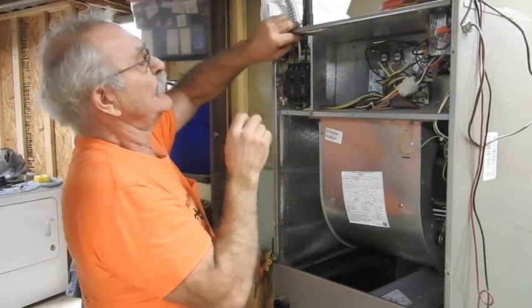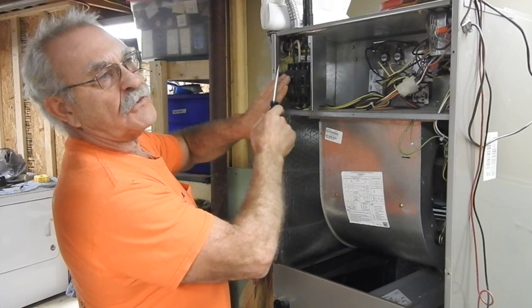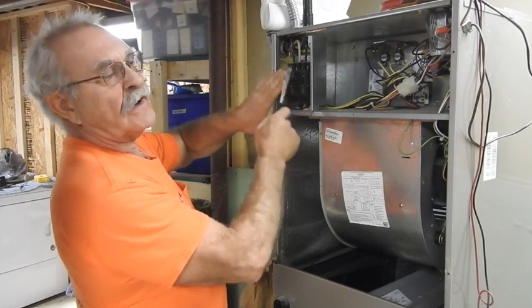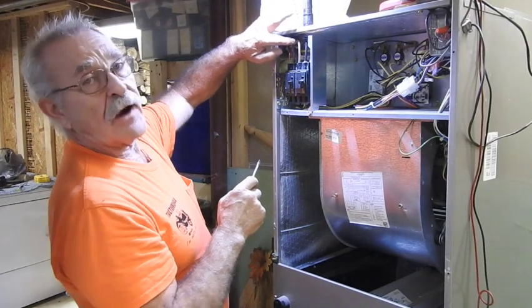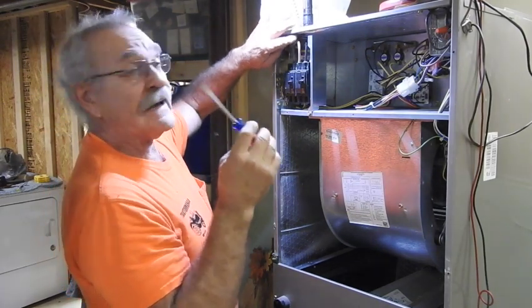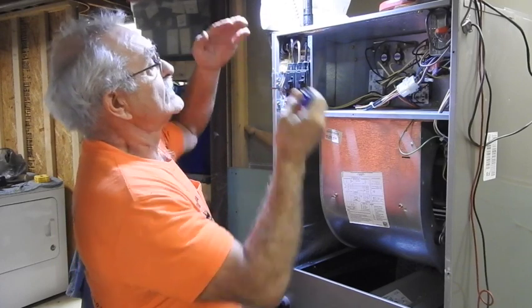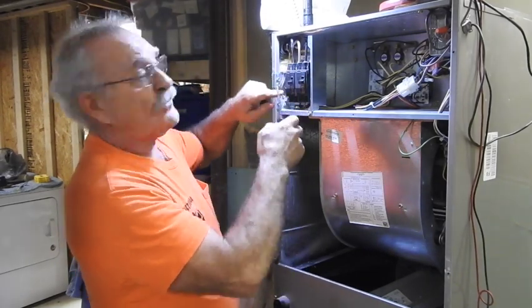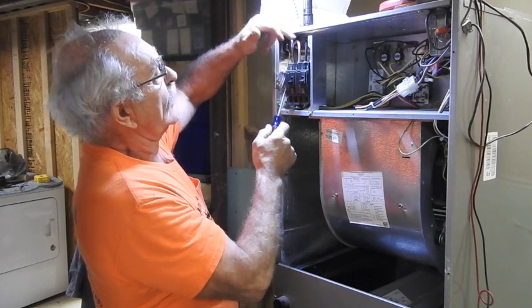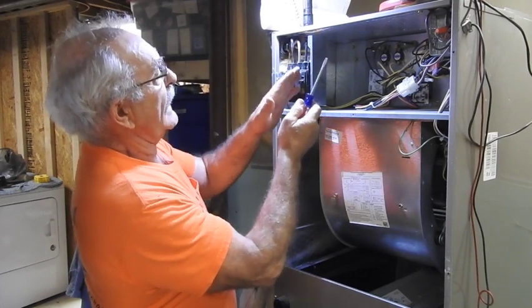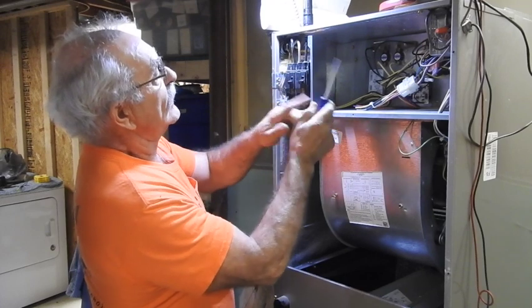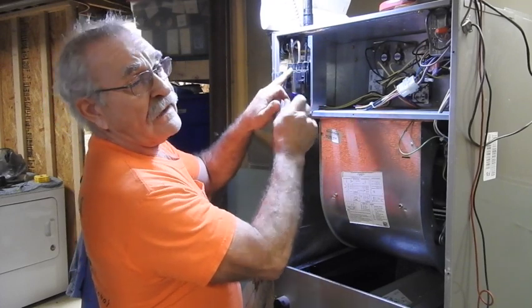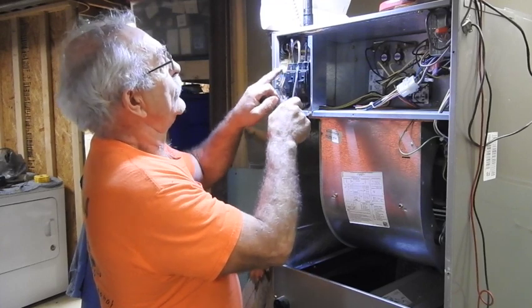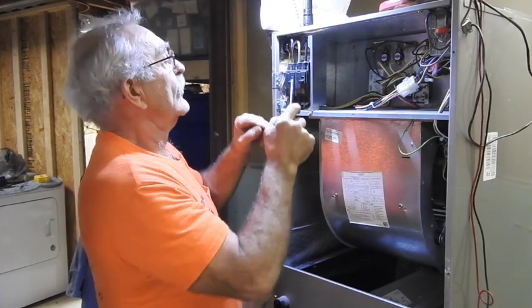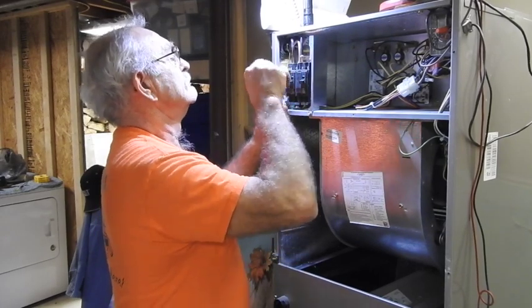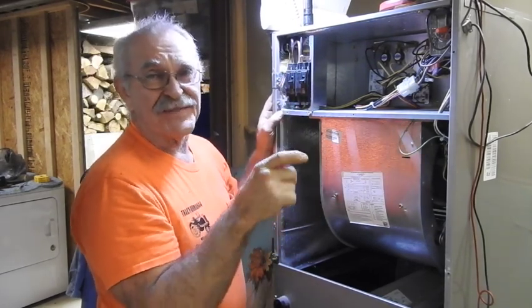If you take a look on a dual element furnace, they're typically marked L1, L2, L3, L4, or L1, L2. You have to make sure that the proper wire off of the circuit breaker that's connected to the bus bars in the main panel box is coordinated with the proper terminals over here. So you can see here is black, white, black, white. L1 and L2 is white, black. L3 and L4 is white, black. So L1, L3 are the one leg off the bus bar in the panel, and L2 and L4 are the other legs. That's how you get your 240 volts. Again, this is something that you as a homeowner should not be doing.